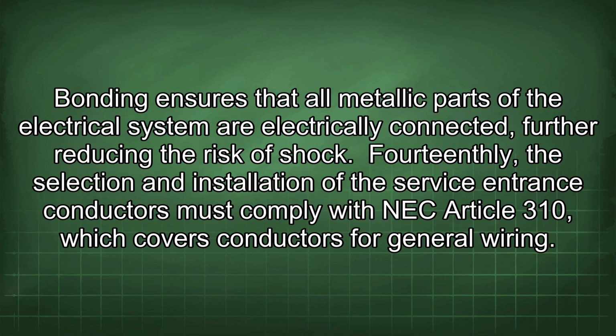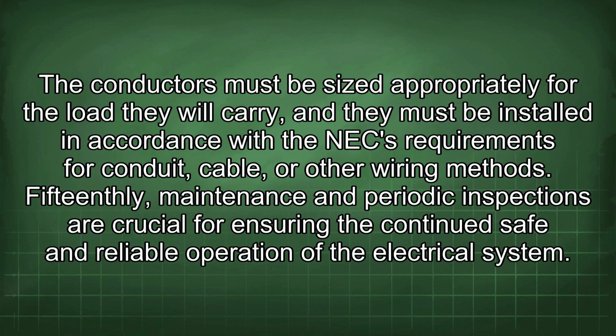14thly, the selection and installation of the service entrance conductors must comply with NEC Article 310, which covers conductors for general wiring. The conductors must be sized appropriately for the load they will carry, and they must be installed in accordance with the NEC requirements for conduit, cable, or other wiring methods.